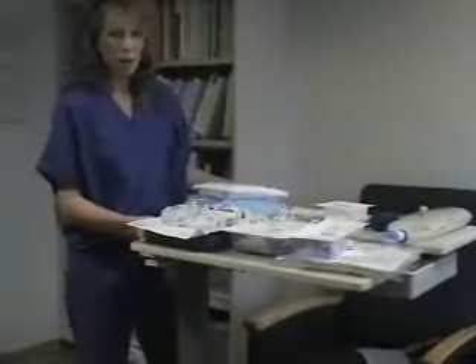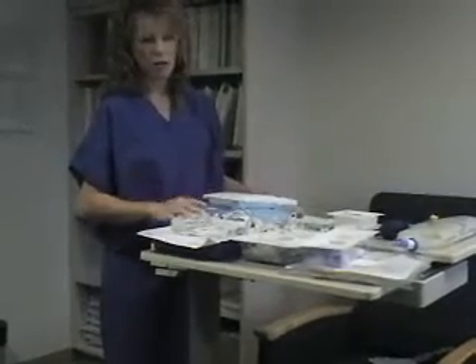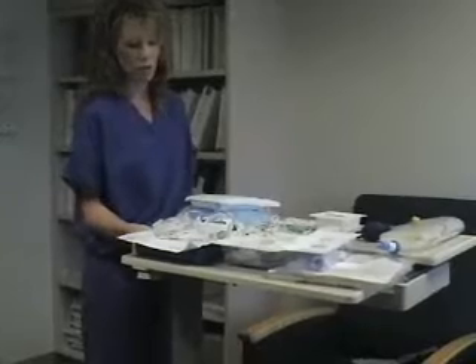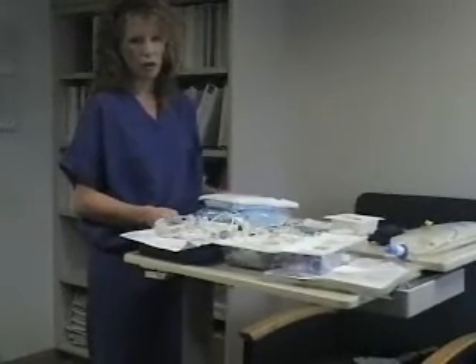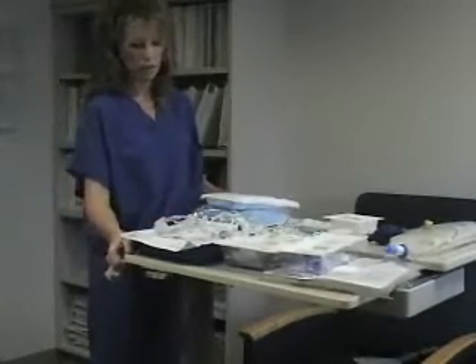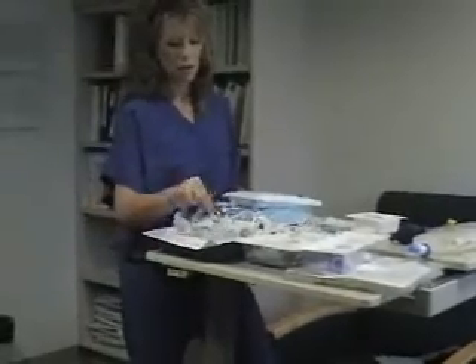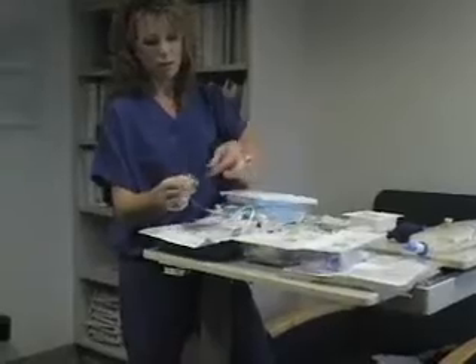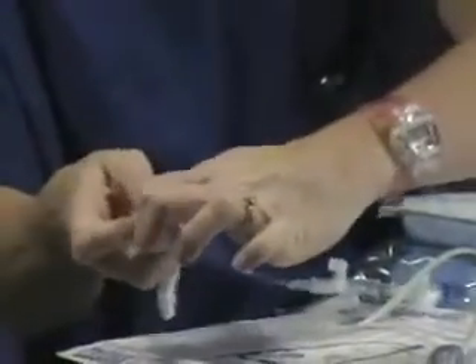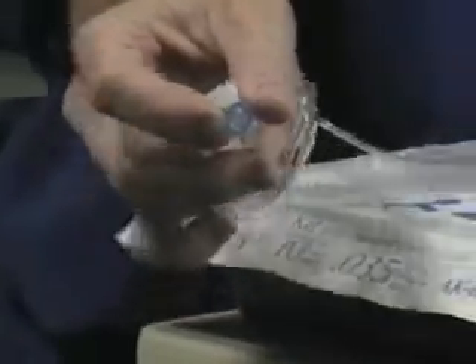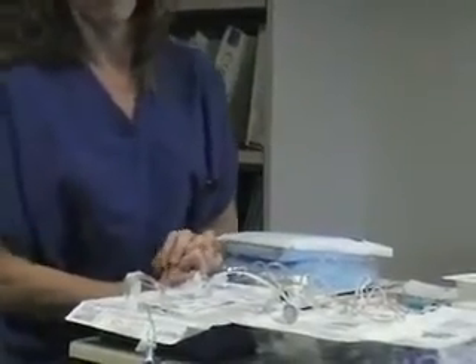The physician will choose the site on the patient, and you just need to make sure that he or she has a tray available in reach to be able to work in close proximity to the tray and the patient. And your job will be to hand he or she the ends of these catheters, and by using sterile technique, you will be asked to open this and connect to the Swan-Ganz catheter once he has the percutaneous introducer into the patient. You will need, prior to that, to have connected the transducers to the pressure cables on the monitor and zero those to the appropriate level on the patient to ensure that when the physician is putting the catheter in, he can obtain accurate insertion waveforms and pressure readings.